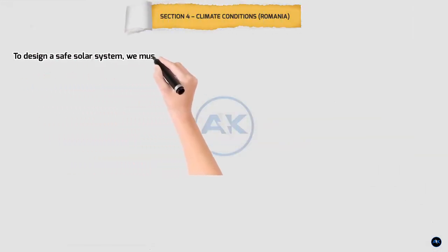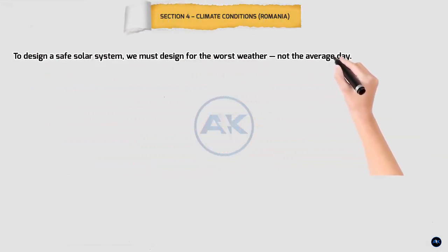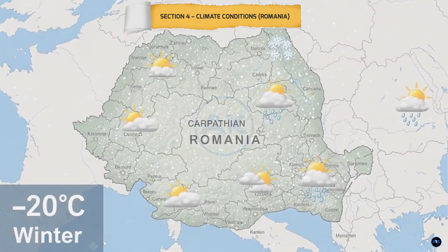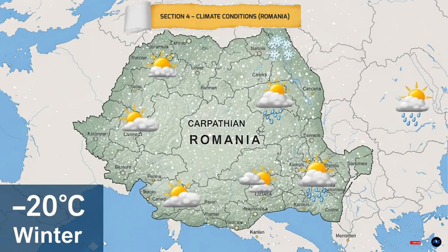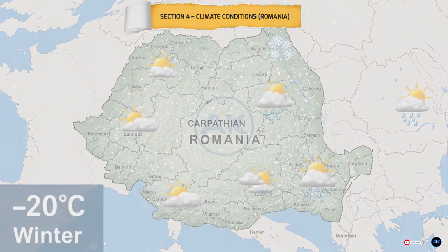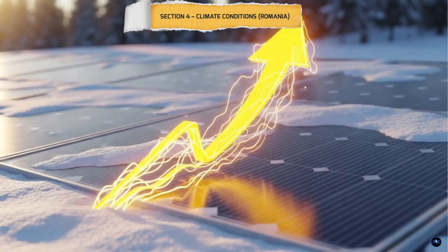To design a safe solar system, we must design for the worst weather, not the average day. This system is located in Romania, where winter temperatures can drop to -20 degrees Celsius and summer temperatures can rise to +50 degrees Celsius. These extremes have a direct impact on solar panel voltage. When it's cold, solar panels produce higher voltage. This is when inverters are most at risk.